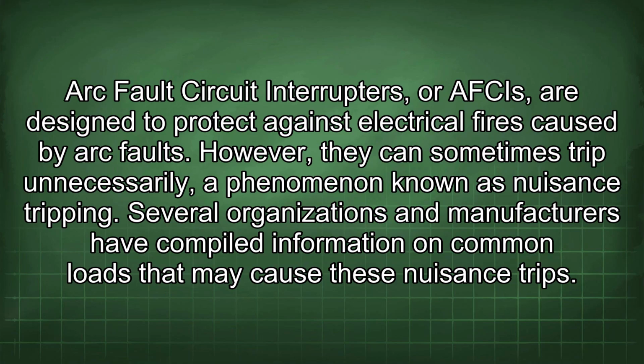Arc fault circuit interrupters, or AFCIs, are designed to protect against electrical fires caused by arc faults. However, they can sometimes trip unnecessarily, a phenomenon known as nuisance tripping. Several organizations and manufacturers have compiled information on common loads that may cause these nuisance trips.